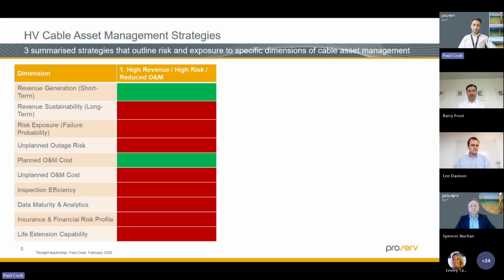Through this approach, export and inter-array cables typically degrade through electrical and thermal cycling from high and low loads, particularly around the terminations, mechanical fatigue around free spans from environmental movement on the seabed and around the cable section, burial loss and exposure, and third-party damage risk.